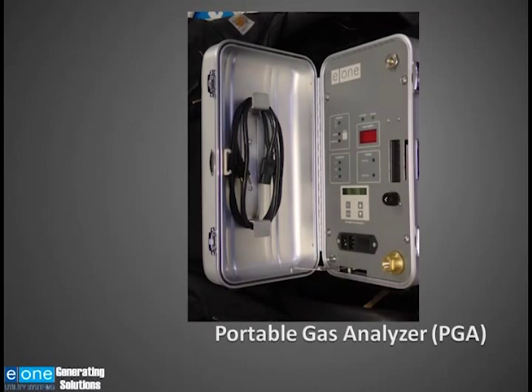This is a picture of a portable gas analyzer, which again I recommend the use of as a redundant analyzer during the purging process. This analyzer is not rated for a hazardous area, and it's designed to be used in a well-ventilated, safe area.